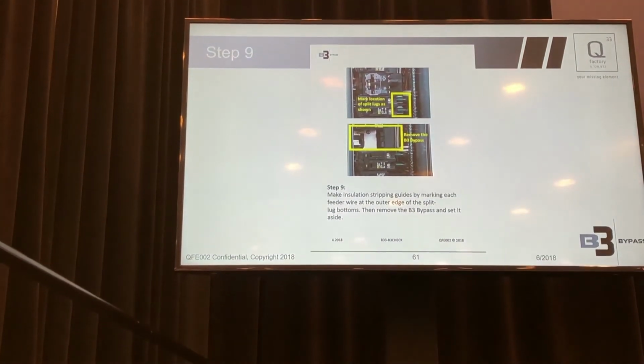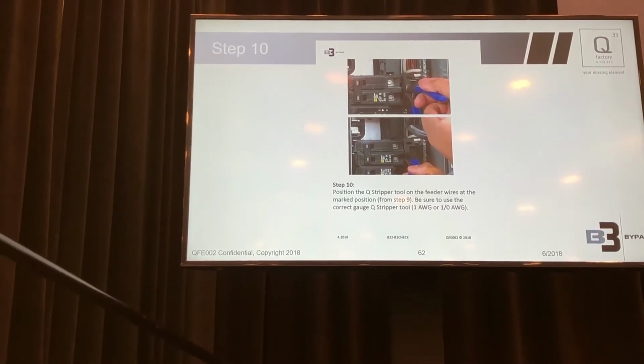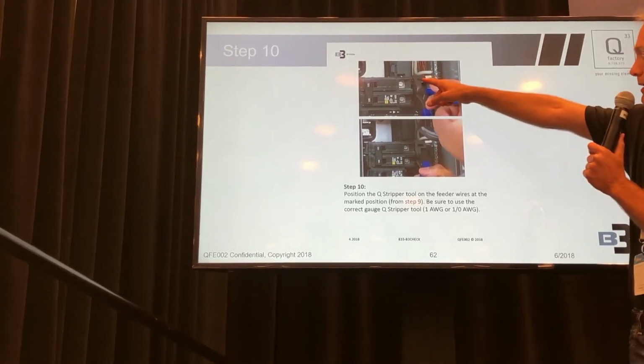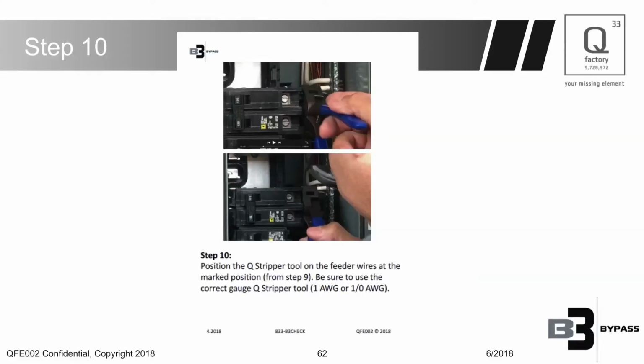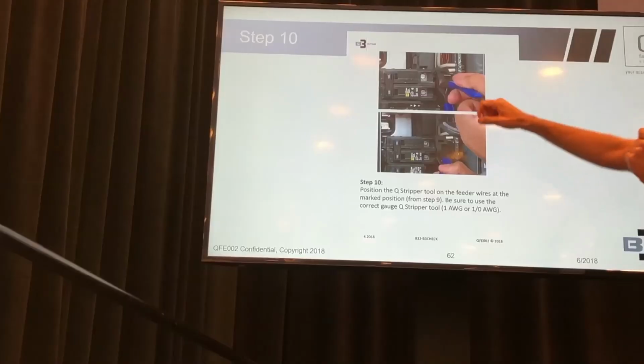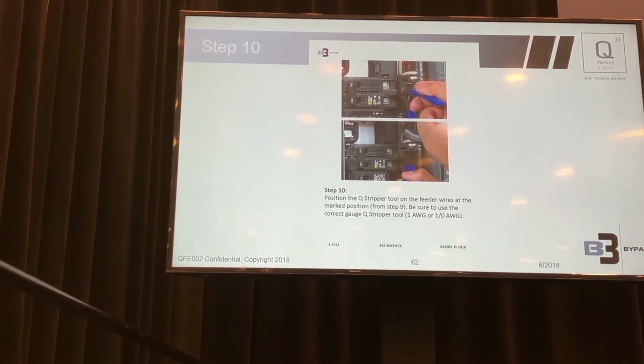After you mark it, take the B3 back out, and now this is a step where you're going to use the tool. We have the Q stripping tool, which you can look at in the booth. There's a little window where you can see where the marking was. Go in and close the Q stripper. You squeeze it down. It's got 6 cutting blades on it. You do a quick turn up and down, a quick rotation against the feeder wire, and it will strip that insulation without damaging the conductor.